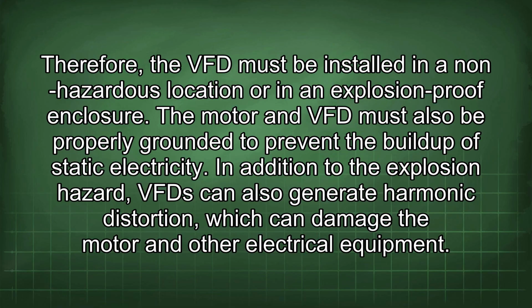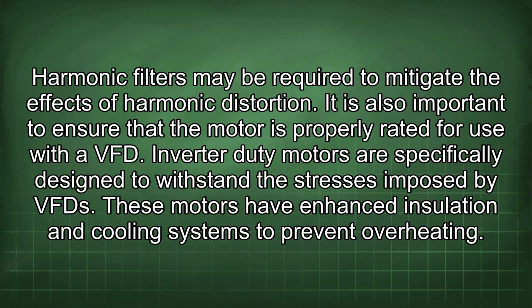The motor and VFD must also be properly grounded to prevent the buildup of static electricity. In addition to the explosion hazard, VFD can also generate harmonic distortion, which can damage the motor and other electrical equipment. Harmonic filters may be required to mitigate the effects of harmonic distortion. It is also important to ensure that the motor is properly rated for use with a VFD.